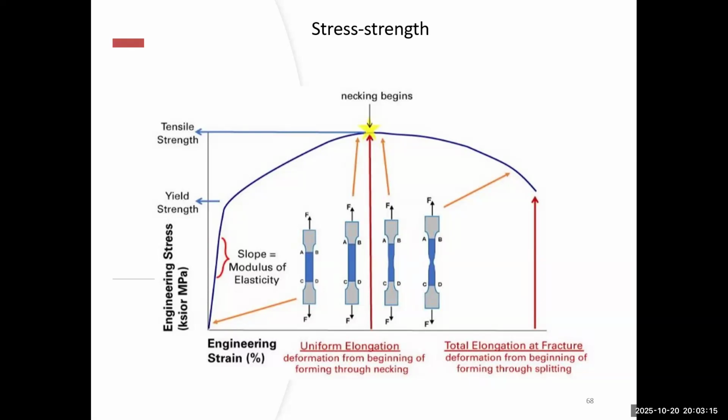And then we consider the strength. So what is the strength? It is the door's fire resistance rating. Let's say it is the ability to withstand heat for 60 minutes, but not every door is identical. Due to different manufacturing and installation, the actual failure temperature of the population of 60-minute doors is also a random variable with its own distribution FR.